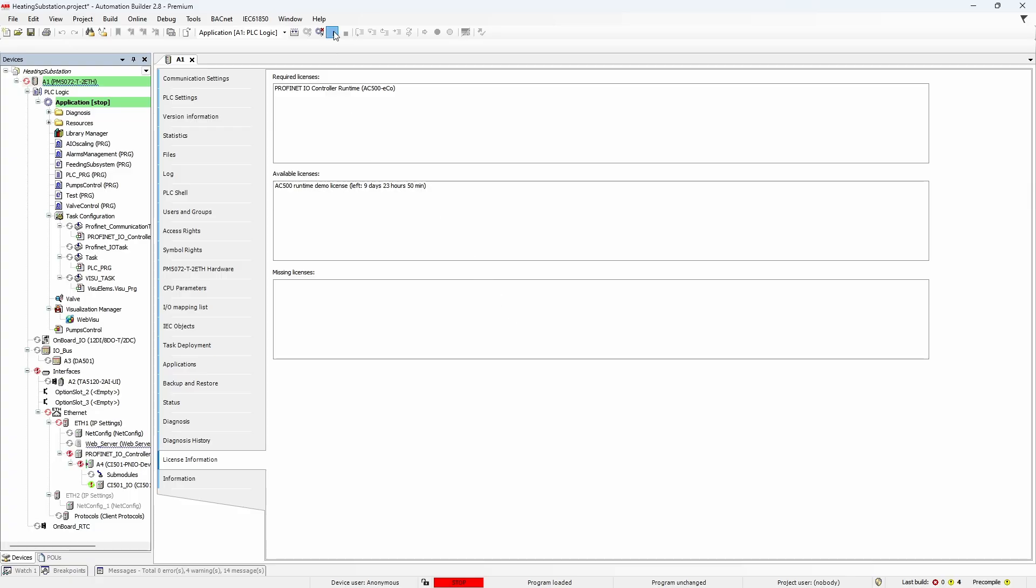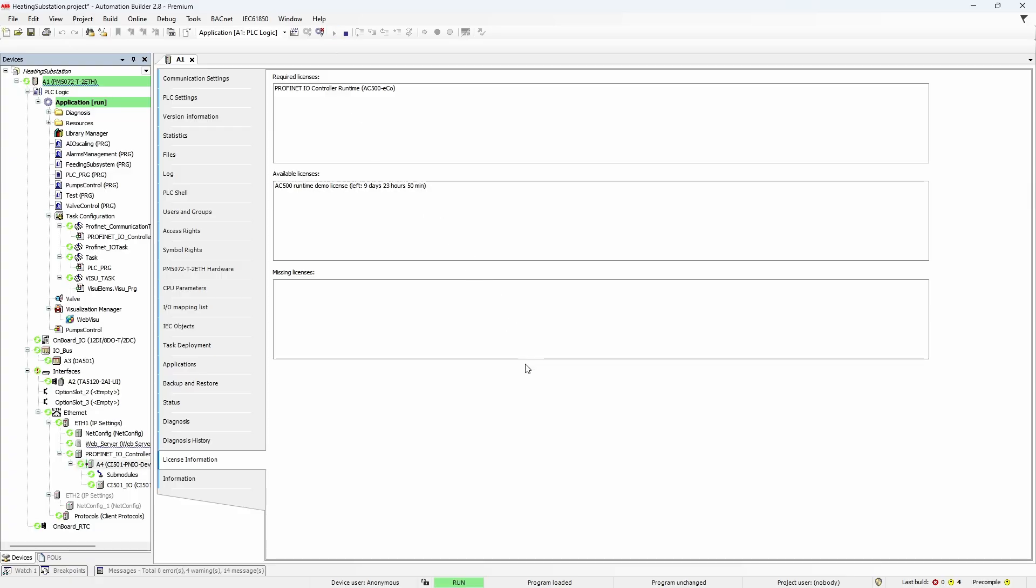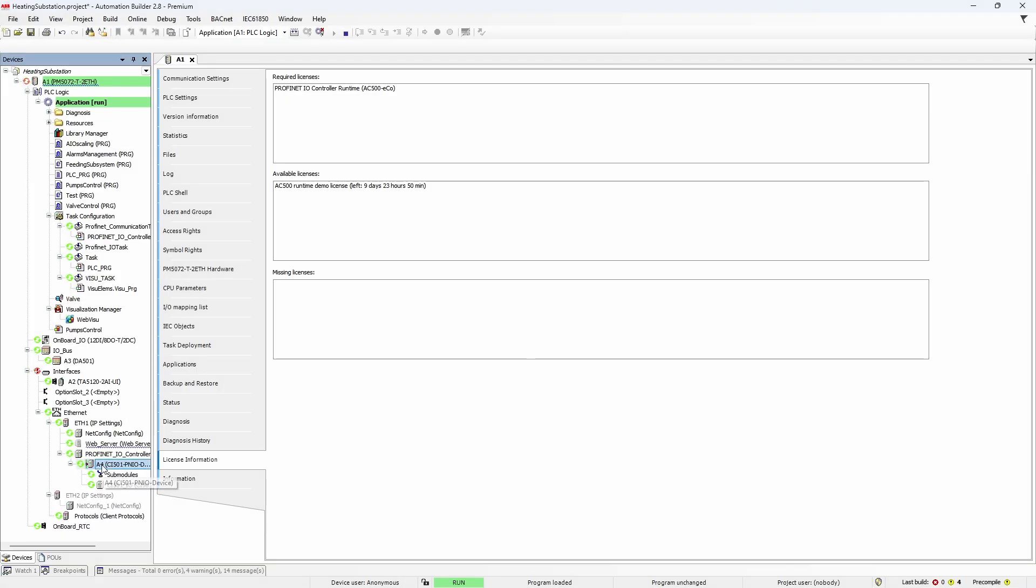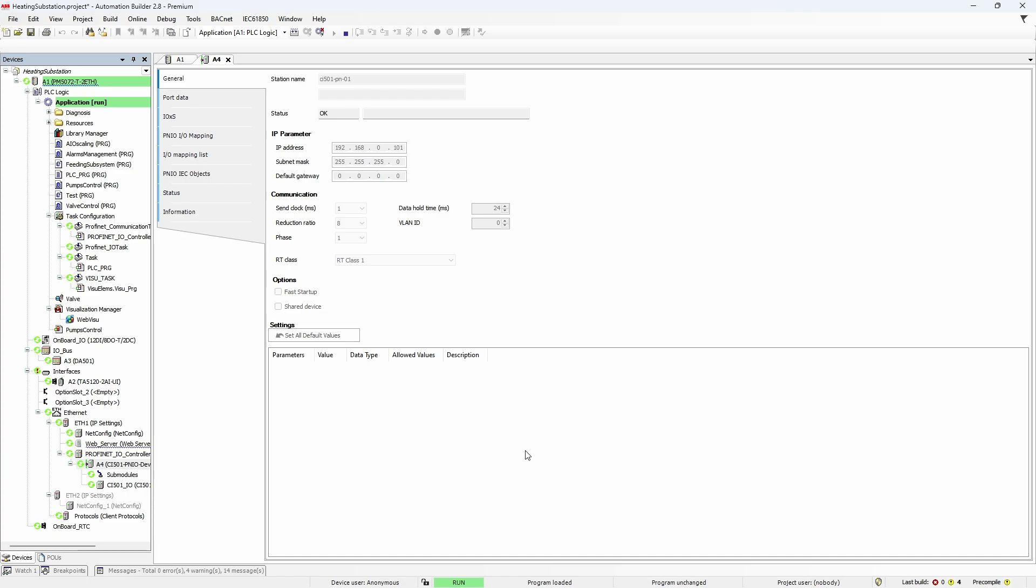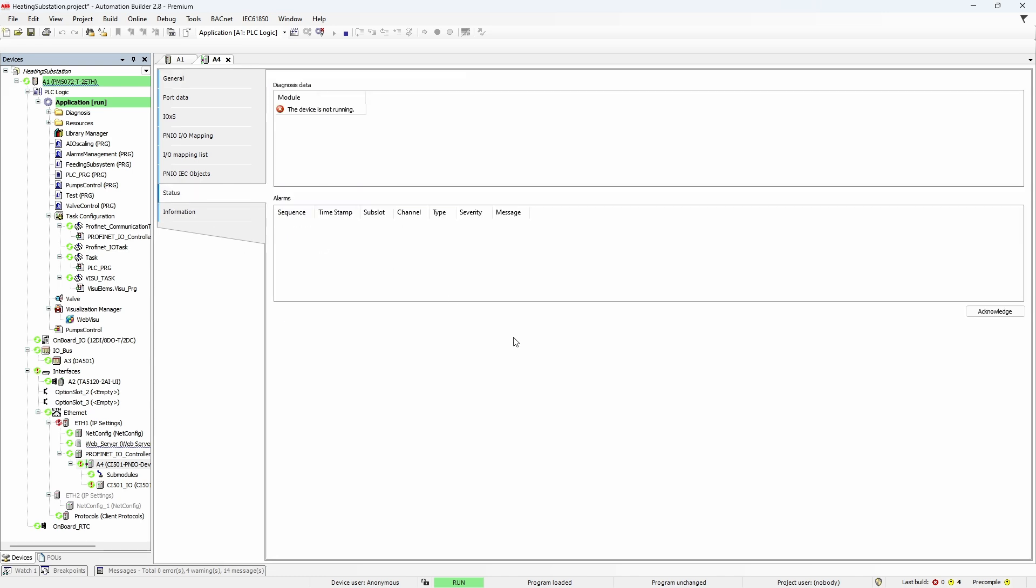The controller should establish communication to the device. And as a result, CI501 station in the project tree turns green. Status string should also say OK. What if we disconnect the cable from the I/O station? Status message will indicate that the controller cannot find a device with such a name. On the status tab, there will be the device is not running message. And CI501 element in the project tree will be highlighted with exclamation mark.